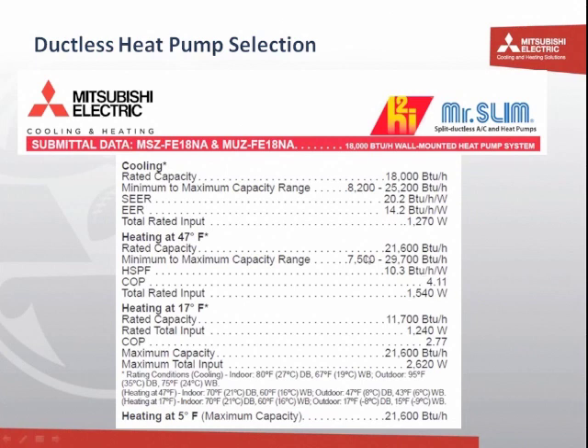Heating similarly, and as I mentioned earlier, the heating capacity on these systems tends to be somewhat higher than their nominal cooling capacity. In this case, at 47 degrees, the system is able to produce 21,600 BTUs. Similarly, you've got the range through which it will operate and the total input at the rated capacity. So we drop down to 17 degrees. This is the 11,700 BTU rating that would occur if we did not have that hyperheat feature. Fortunately, when we activate the hyperheat feature, it brings it right back up to the nominal capacity. Clearly, there's an energy penalty in doing so. It requires some more electricity to produce that higher output.